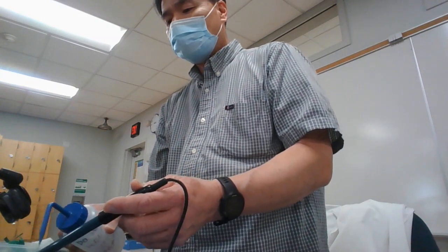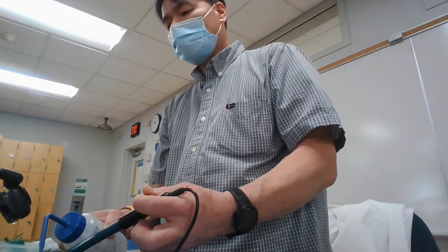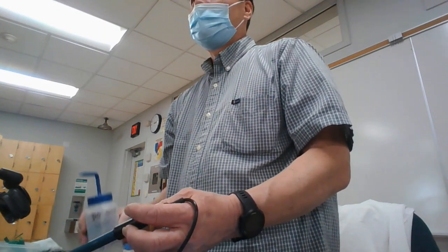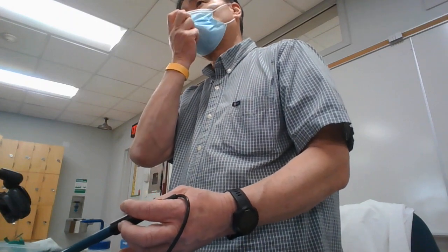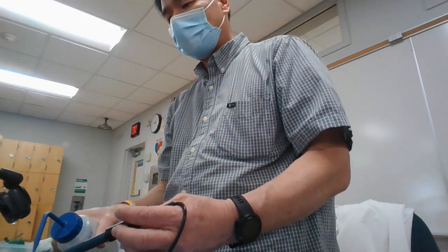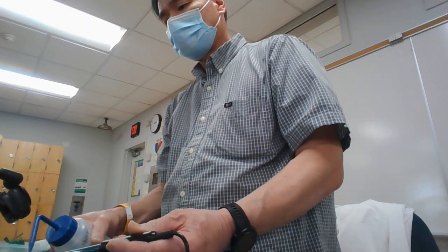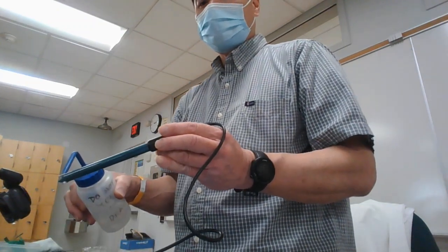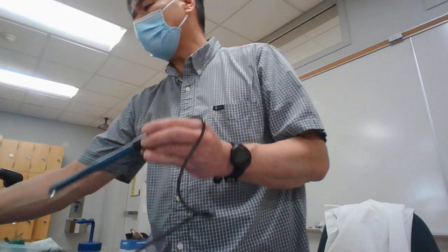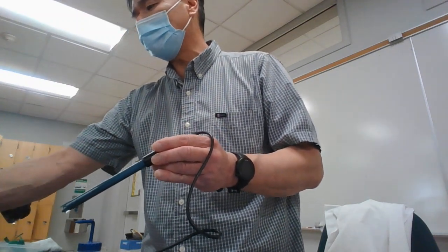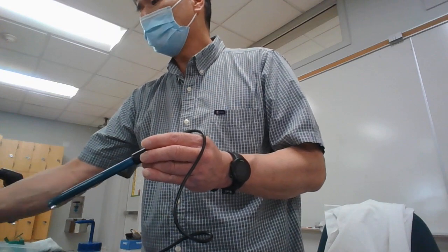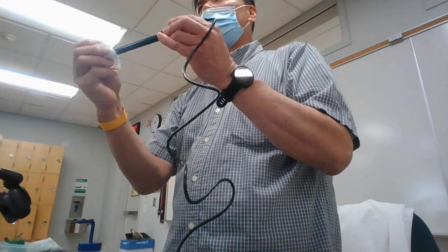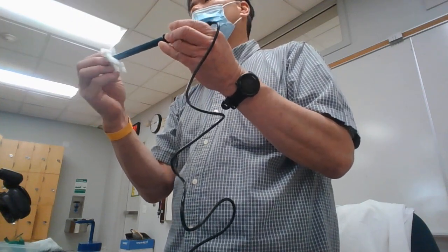Okay, so rinse off the bulb. In fact, we want to keep the bulb hydrated at all times. It's a gel membrane. If the gel membrane dries out, it makes the pH probe very unresponsive, and you have to rehydrate it, which takes time. So thoroughly rinse off the tip of the probe with DI water. Now it's wet with DI water, but we don't even want to contaminate the buffer solution with DI water. And so we're going to get a Kimwipe and dry the tip of the pH probe and the bulb as best you can.